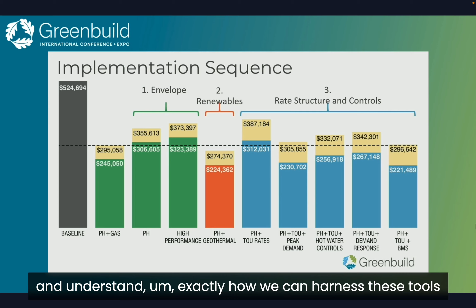The next set of controls we looked at is hot water control. This is a singular approach which drives exactly at the end use that is driving the utility gap penalty, which is domestic hot water, something we traditionally have not been able to control. The concept is it pushes the energy use that would be used to heat the water at peak times to off-peak times by preheating it in the early hours of the day, so the energy used to get it up to temperature is much smaller.